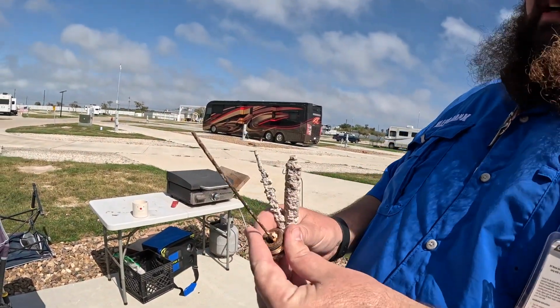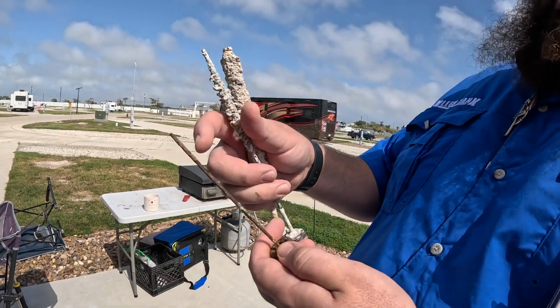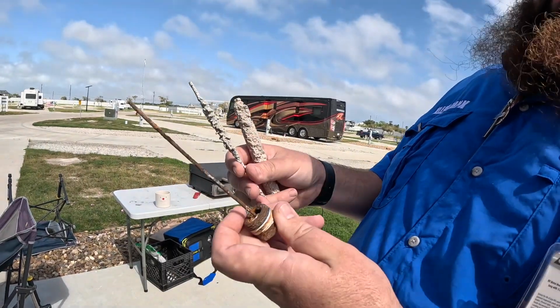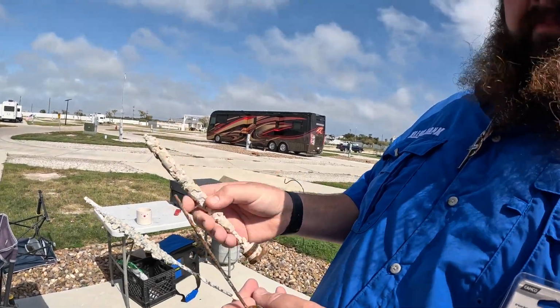And this is about 3 years past done. It actually started eating the rod on the inside. So make sure you replace it before you get to this or this. Start getting one on order when it's about here.